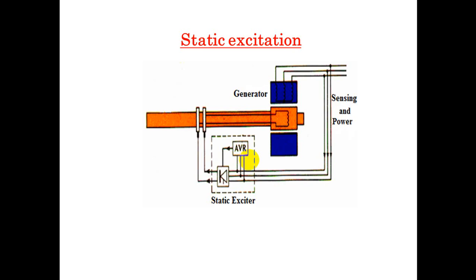This is the next method, as shown in these pictures. It's called static excitation, or the general case, replaced with a diode bridge, a group of diodes, and the AVR, or automatic voltage regulator, that regulates the voltage output from the static exciter into the AC synchronous generators.